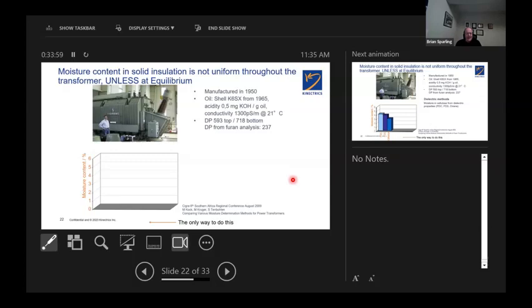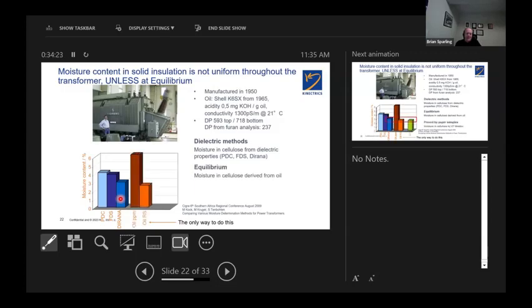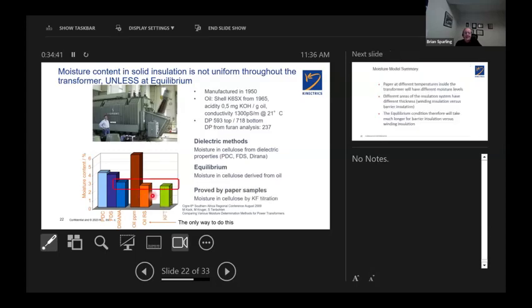Once they achieved that, then they began to apply different measuring techniques. The dielectric things like frequency domain spectroscopy, FDS, the Dirana product, they were measuring between 3 and 4% total water content in that block of solid insulation. The equilibrium based on Karl Fischer test of oil was vastly overstated. That's why we don't use ppm water in oil. Forget about it. Use the oil saturation values, the measured oil saturation. And here it was around 2.5%. And then the proof in the pudding, so to speak, was once it was all said and done, they went in and they took paper samples out of the transformer and dried them in the lab.